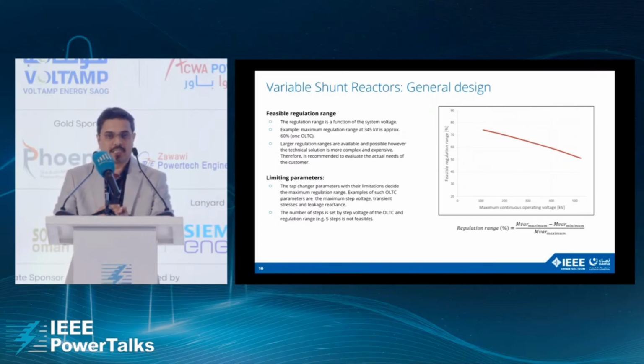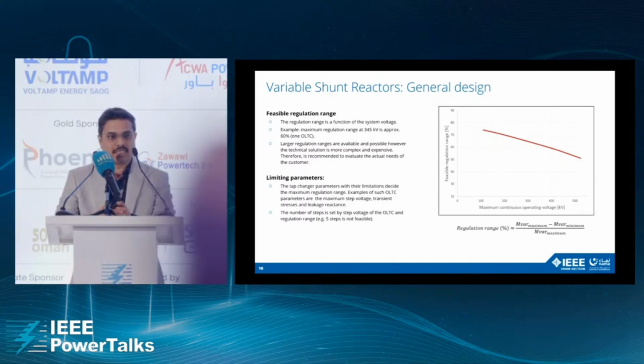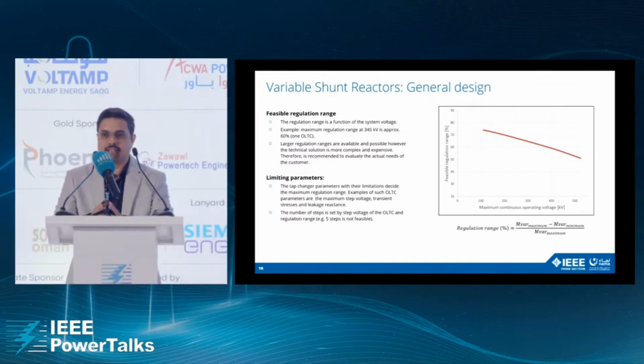So this adjustment or this variance is not a function of the reactor or a limitation of the reactor, but it's mainly decided by the on-load tap changer, which varies the number of turns of a reactor. The on-load tap changer has some limitations, like it has a fixed number of turns, a specific step voltage, specific transient stresses, and specific leakage inductance. So these limitations of the OLTC are deciding the different variation possible with a variable shunt reactor.